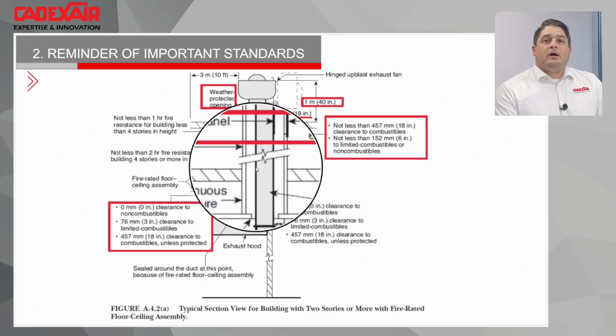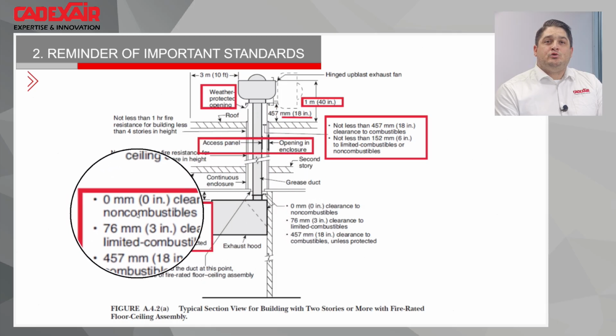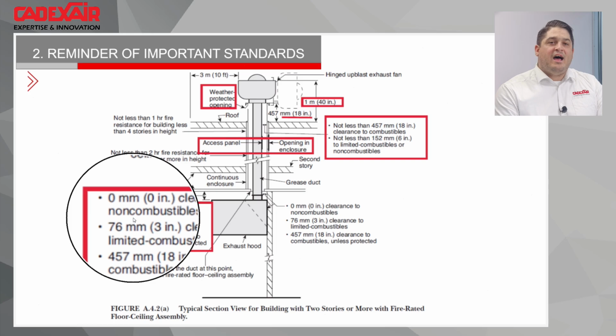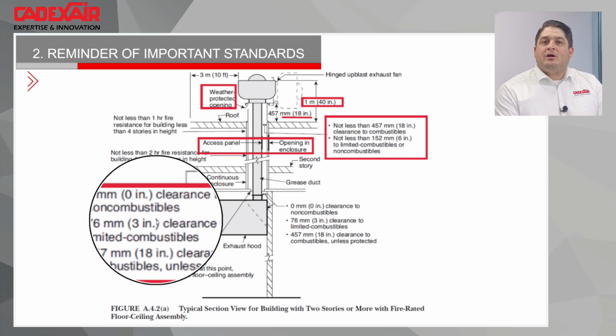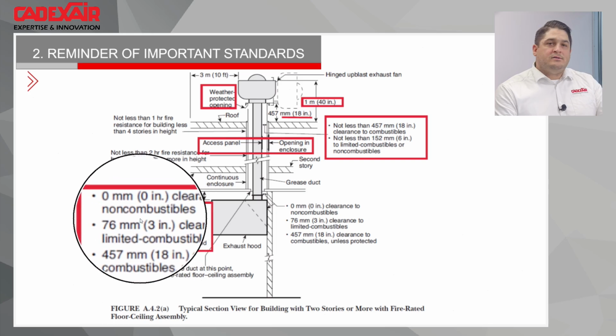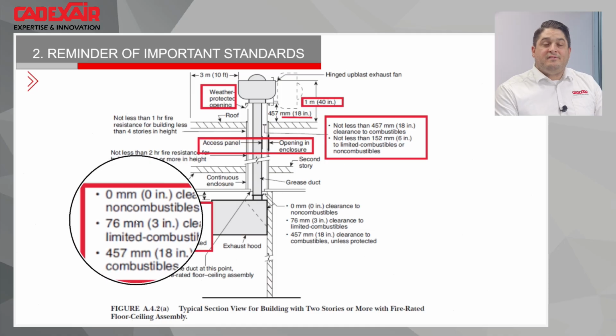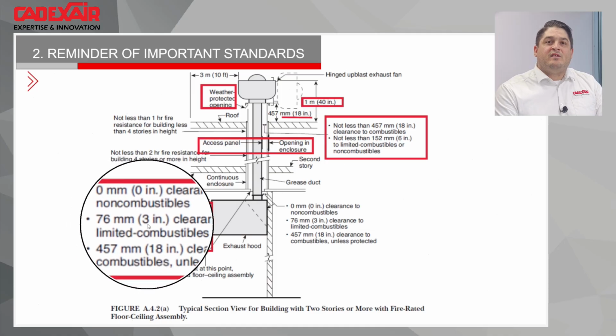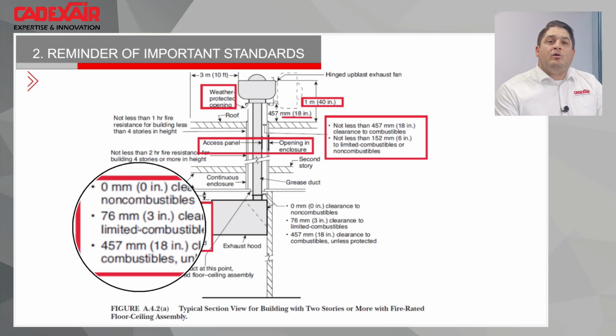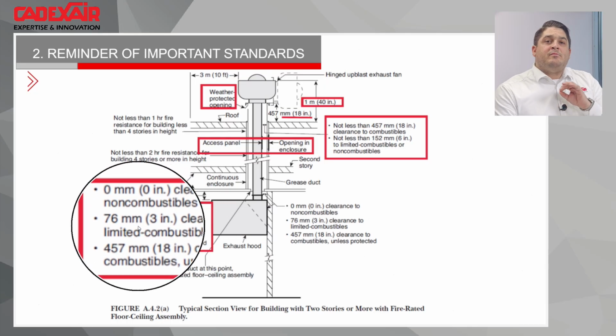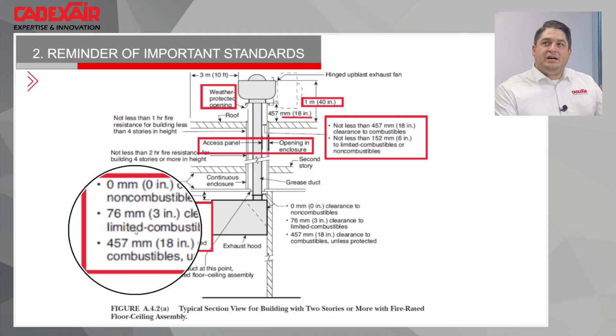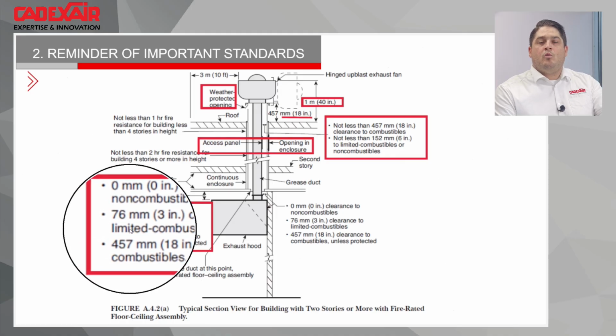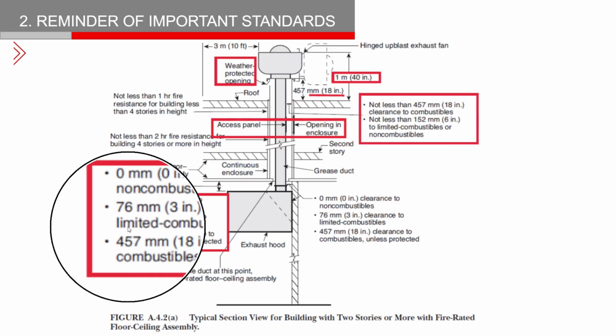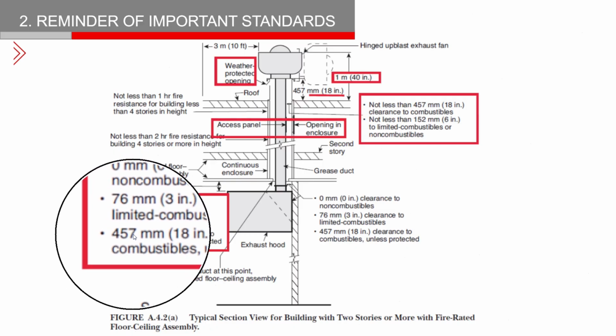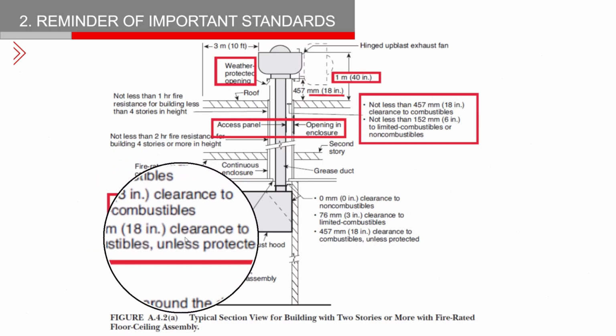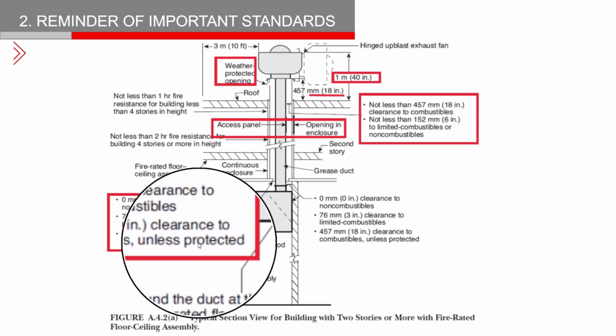Everywhere when we work with NFPA 96, they will ask you to have, for the hood, the duct and the fan, 0-inch clearance to non-combustible material. So a hood can be on steel, concrete, anything non-combustible. Then 3-inch clearance to limited combustible. The most common limited combustible in the world is gypsum. So you're not allowed to put a hood directly on the wall; you need to put a 3-inch spacer in the back. It's pretty easy and common in the industry. And after that, you need to have 18-inch clearance to combustible material for the hood.